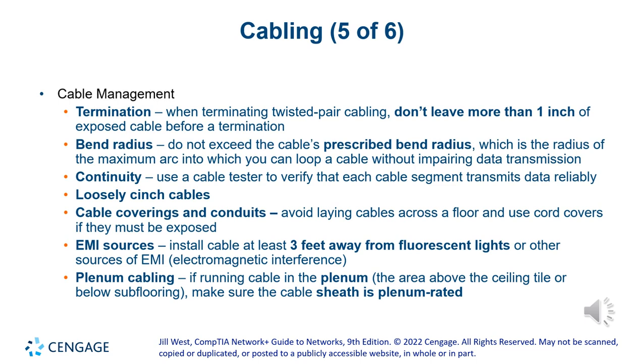When you loop a cable, like if you're trying to coil up the cable, also don't coil up really small circles, because that can damage the cable if you go beyond that prescribed bend radius. So you have to make big loops, not 4-inch little loops, but more like 10-inch loops or bigger. You can use a continuity tester that will test your connection, to make sure that from end to end the cable is fine. Sometimes when you're running the cable it gets snagged somewhere or it gets a twist and you pull the cable and you go beyond the bend radius, you can damage the cable. So a continuity test will guarantee that the cable is not damaged.